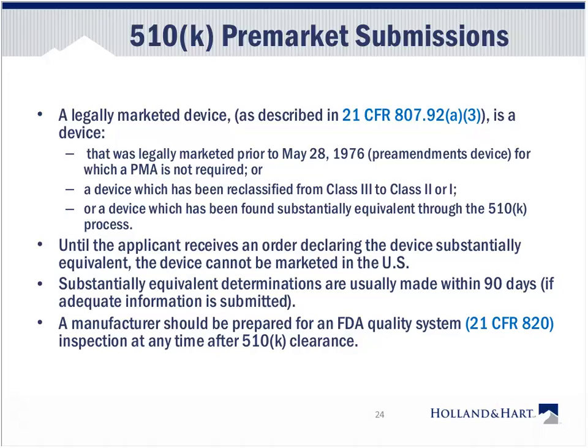And then the third of these points is the most common way that we go about getting clearance, and that is a device is found to be substantially equivalent through the 510K process. Again, we're going to walk through an example. Until the applicant receives an order declaring the device substantially equivalent, the device cannot be marketed in the U.S. I can't stress that enough. If you are going to legally market a device, it must either be exempt from pre-market notification or it must have received pre-market notification, typically through the 510K process.